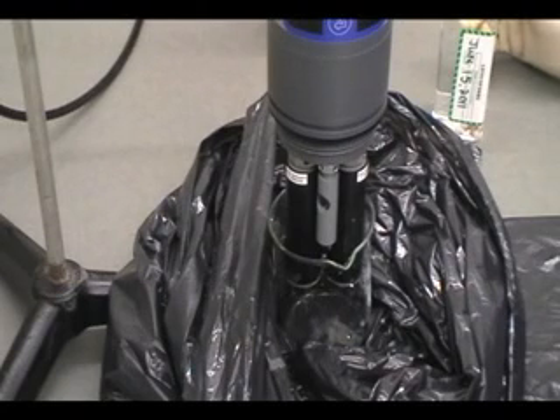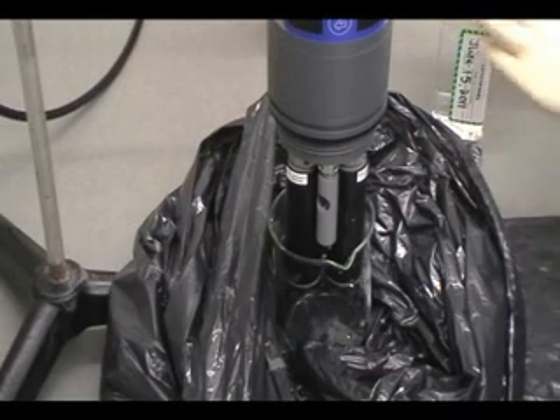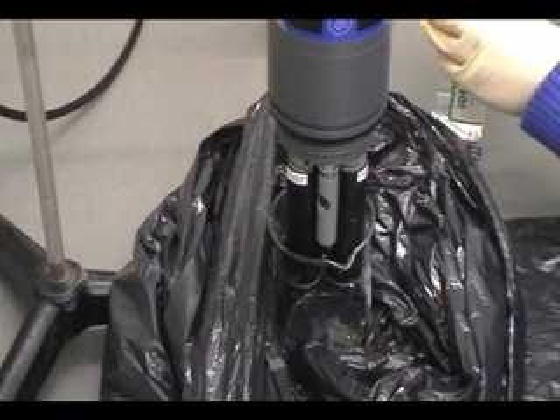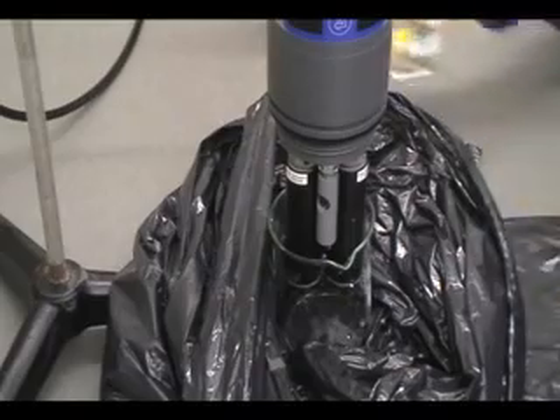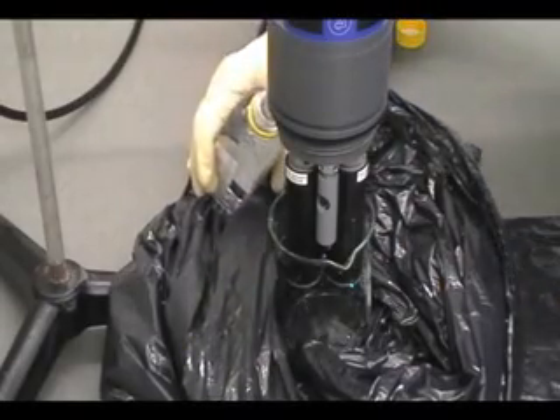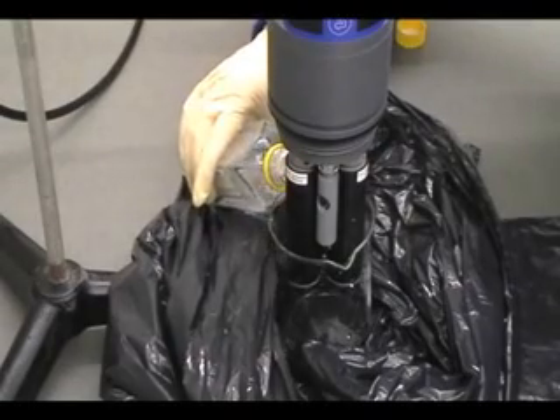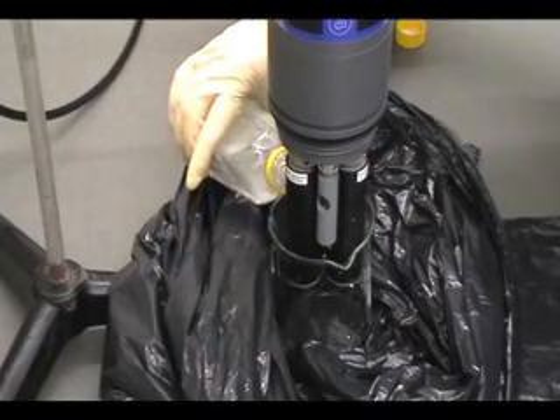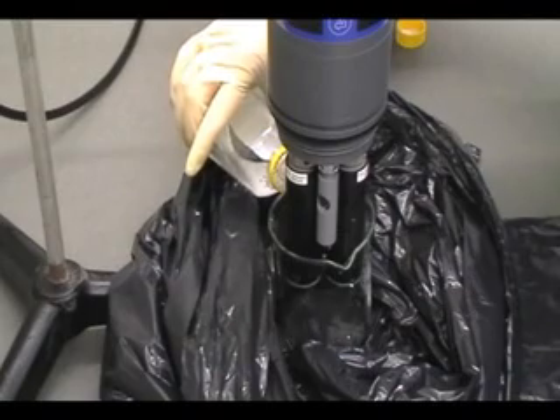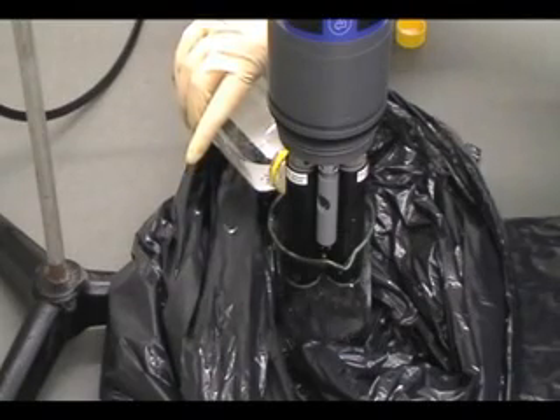Step 2. If the 0 NTU standard is in a jar with a wide enough mouth, lower the sensors into it so that only a few millimeters of turbidity sensor are submerged. Note, this jar should not be plastic. It should be clear or dark glass, and it must be placed on something black.